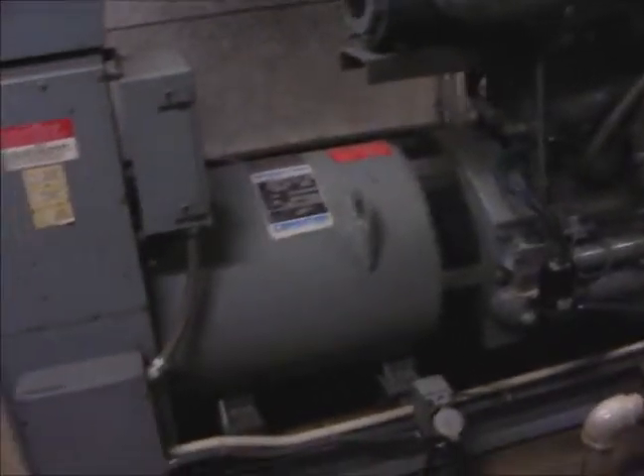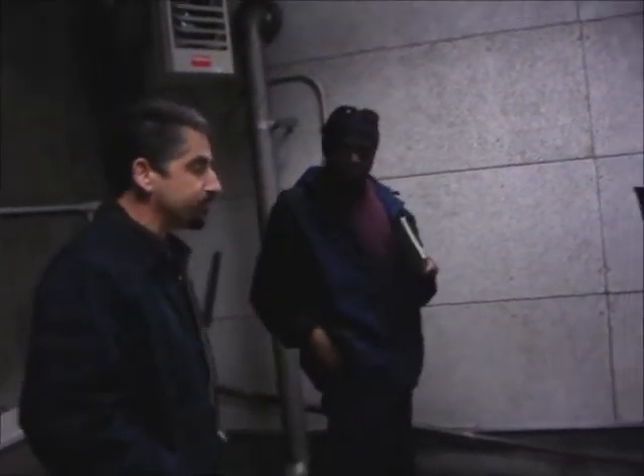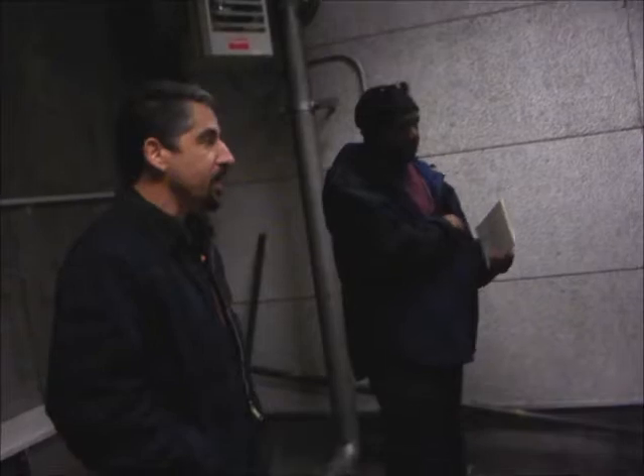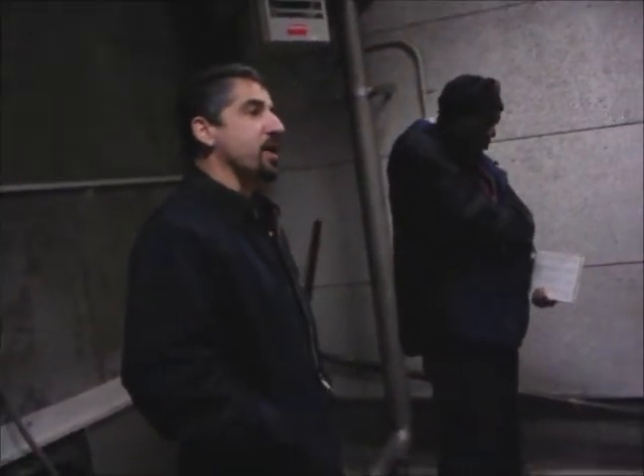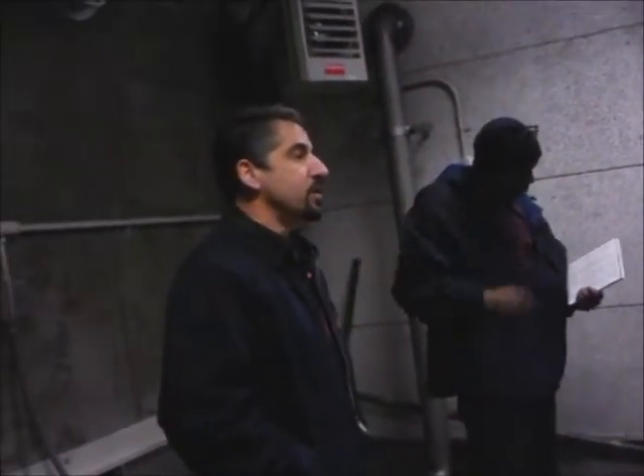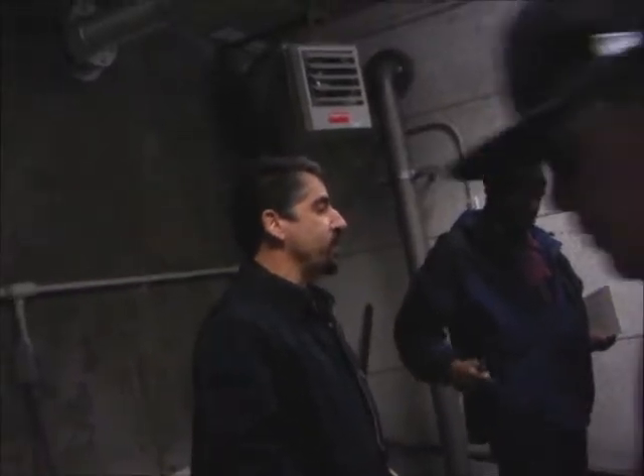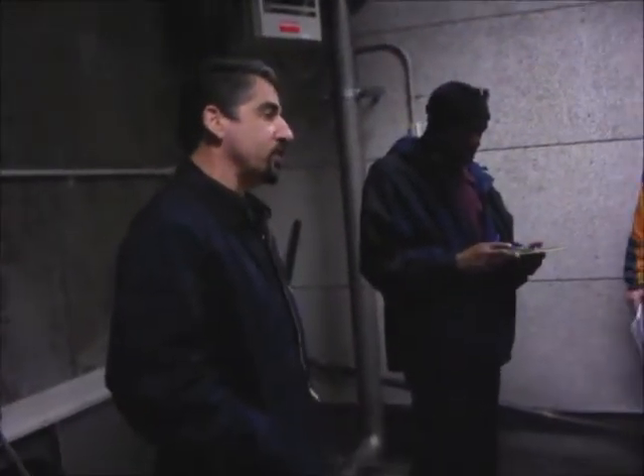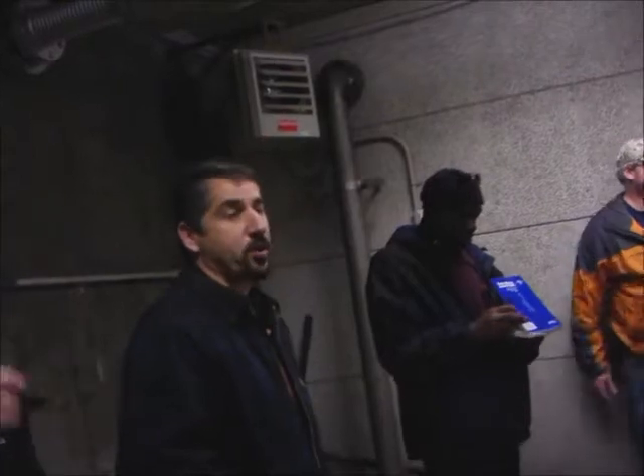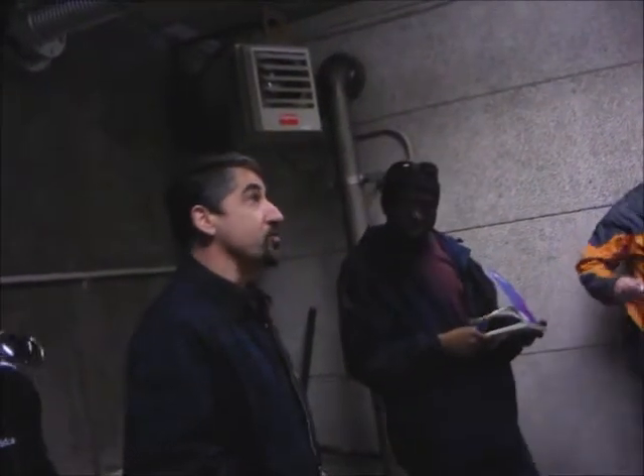Another generator here. Okay, this station has backup generator power, just like the other one, designed to run the station at full load for 24 hours. With the station calling for full demand for 24 hours, everything's automatic, it has an automatic transfer switch. Basically, it senses the power phase or fail off, turns the generator on and switches power over to the generator. We'll switch back after it senses the power has come back. We also get alarms when this happens. We come in and check to make sure everything's working.